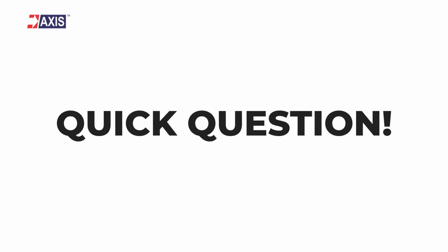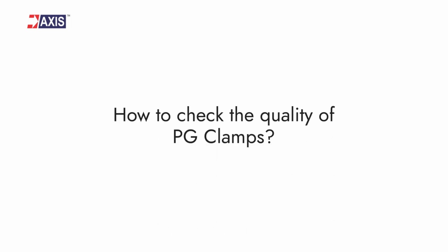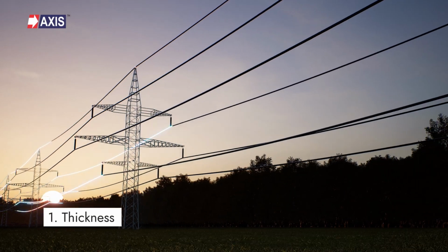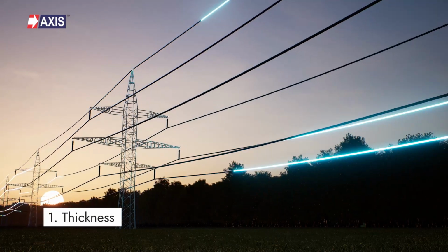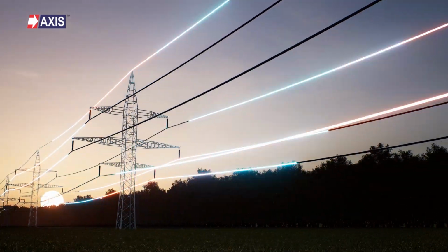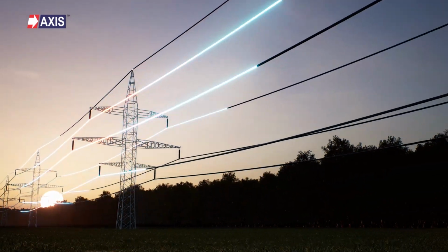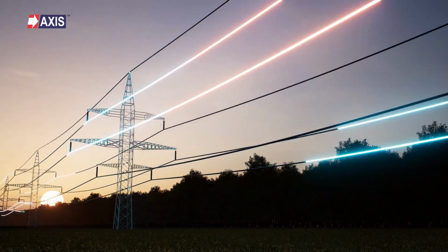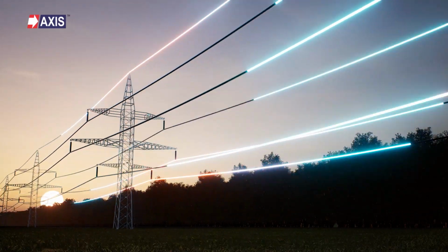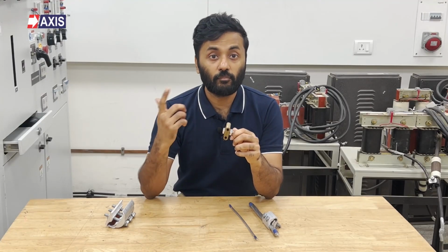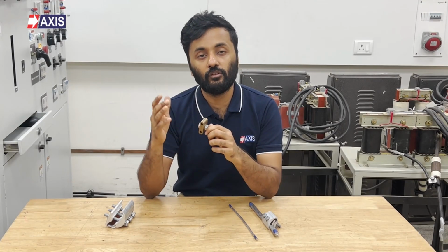A quick question for all of you. How would you check the quality of your PG clamp? I would look at a couple of aspects of my clamps. The first being the thickness. Thickness determines the current carrying capacity of the clamp. If the clamp is too thin for the application, it won't handle the mechanical and the electrical load properly. This can lead to overheating, deformation, or even failure under load.